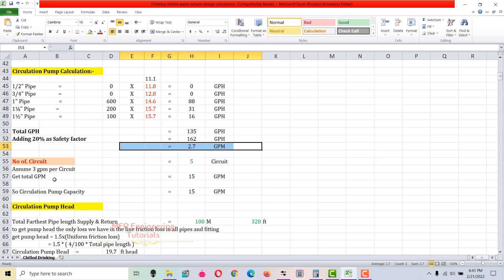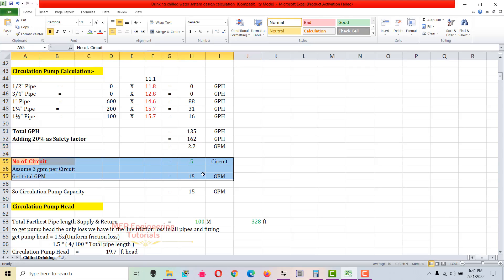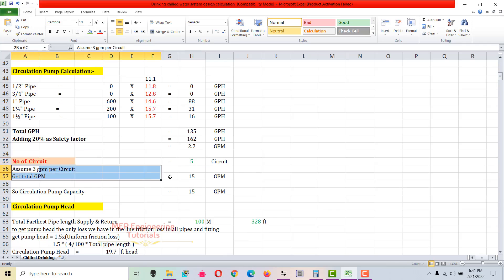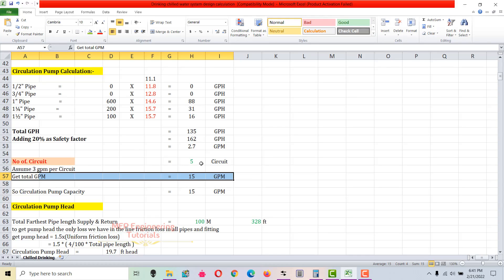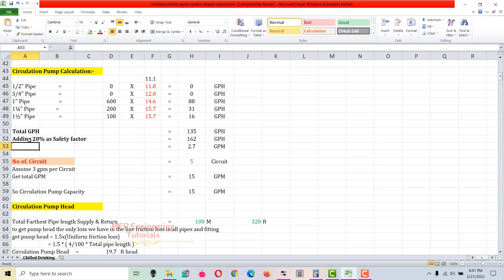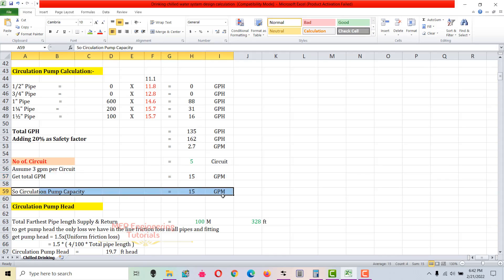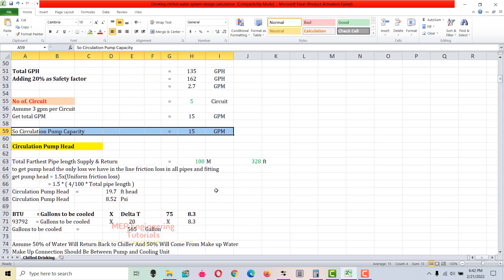The minimum we use is 3 GPM per circuit in chilled drinking water system design. We check the number of circuits from the drawing — let's say we use 5 circuits. Minimum required is 3 GPM × 5 circuits = 15 GPM. Whichever value is greater — 2.7 GPM or 15 GPM — we use as the circulation pump capacity. 15 GPM is greater, so we use 15 GPM.